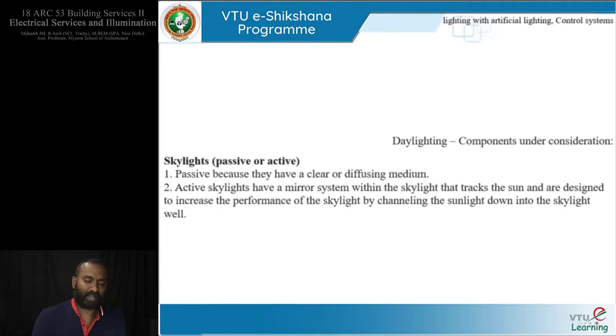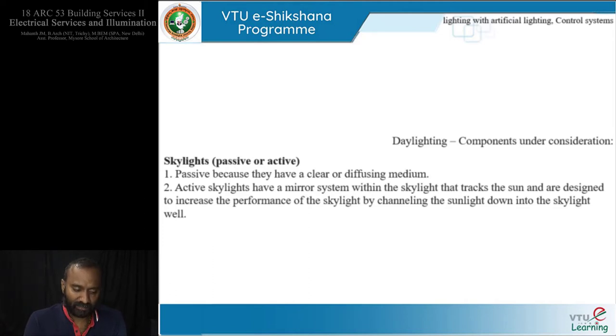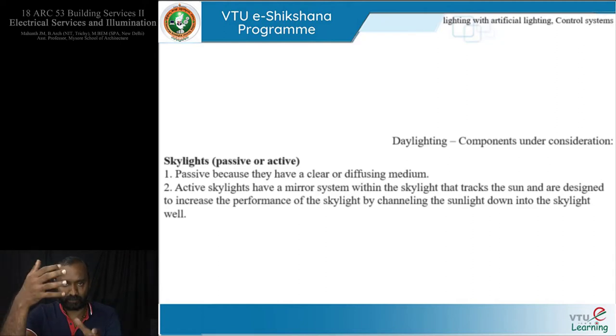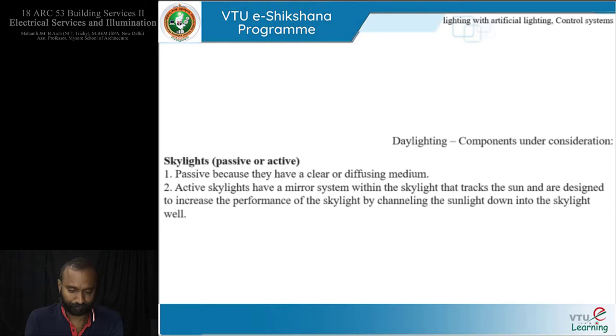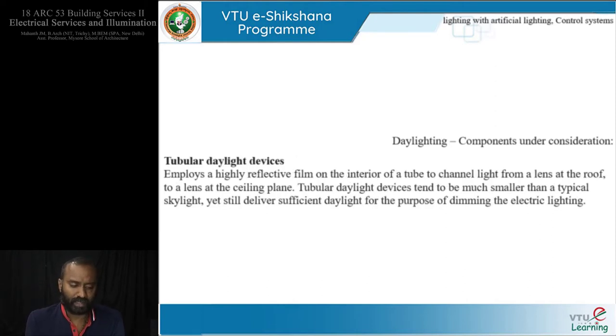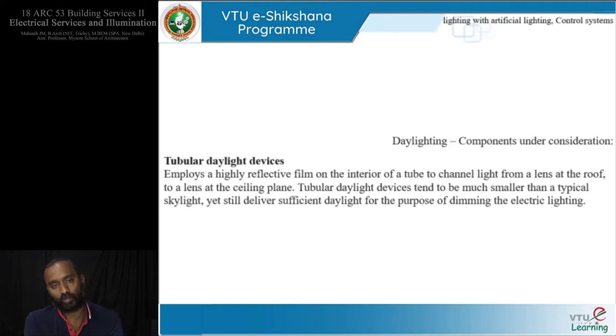Skylights are of passive and active types. Passive skylights have a naturally diffusing medium. Active skylights have a mirror system within the skylight that tracks the sun and is designed to increase the skylight's performance by channeling sunlight down into the skylight well. For tubular daylight devices, the skylight well is replaced with a tube that uses a high-reflective film on the interior to channel light from a lens at the roof to the place where you want it through another lens.